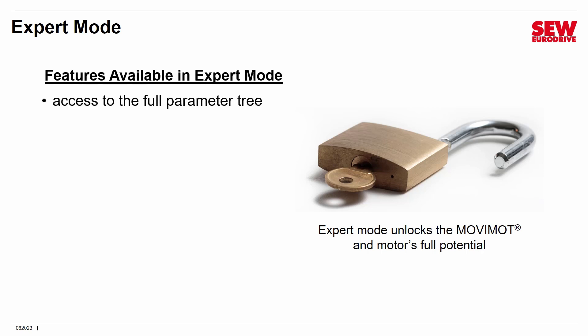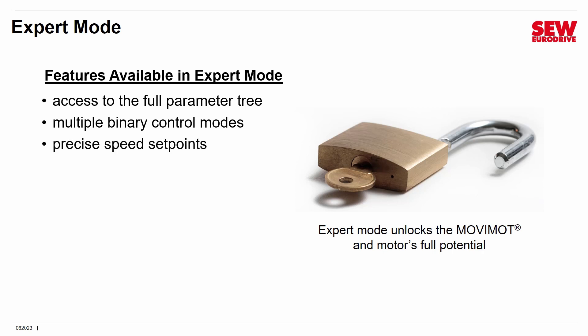So what can you do with Expert Mode? First, you have access to the full parameter tree. In our last session we examined some read-only parameters accessible in Easy Mode, but almost all read-write parameters could not be changed in Easy Mode. Second, you have multiple binary control modes available. In Easy Mode, you just have one, where you can select clockwise, counterclockwise, and switch between F1 and F2 speeds. But Movimot actually has several binary control modes with different combinations of binary inputs.